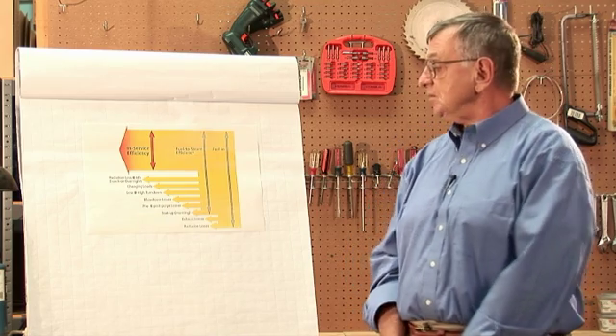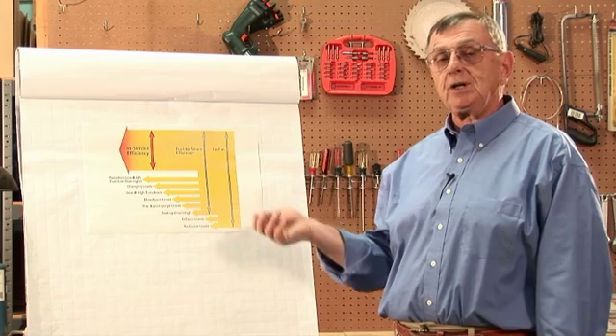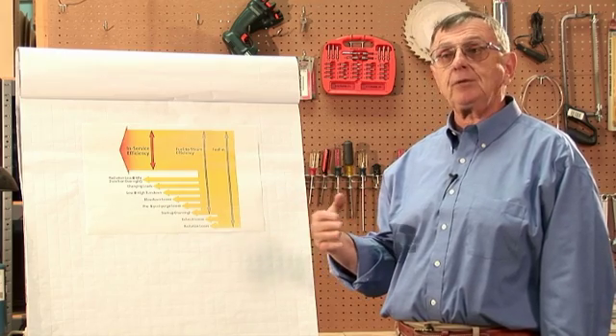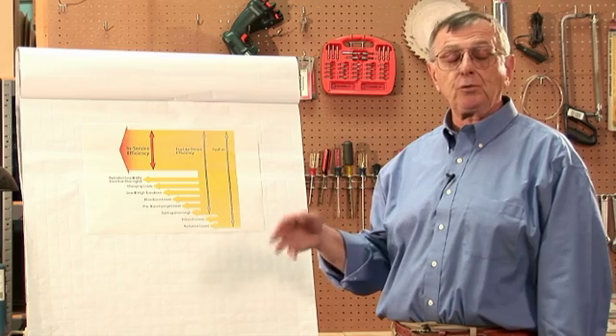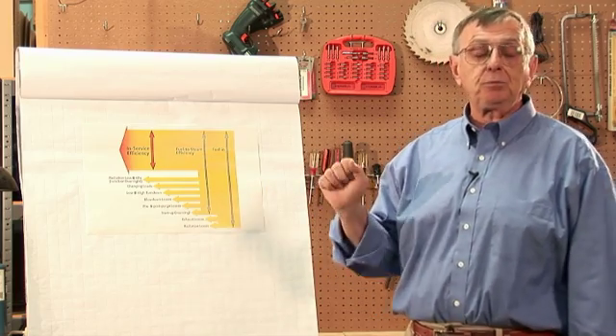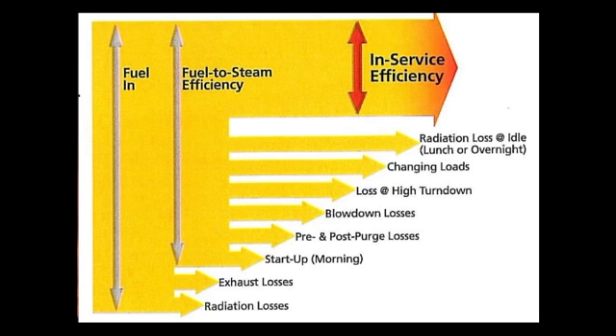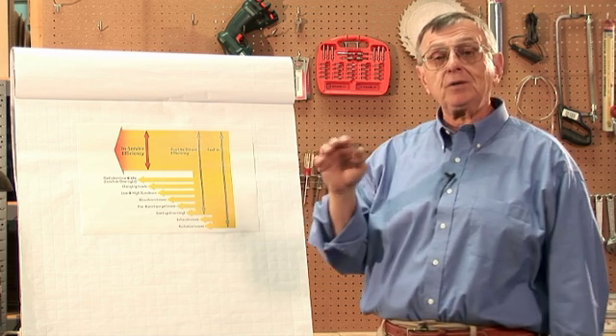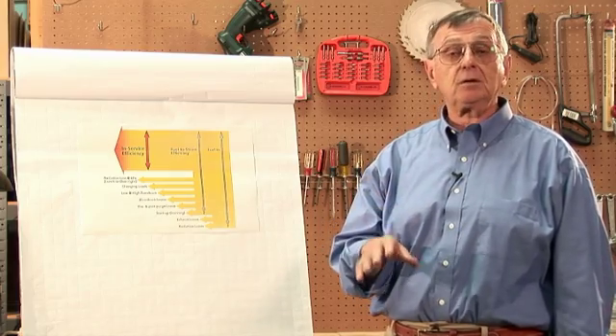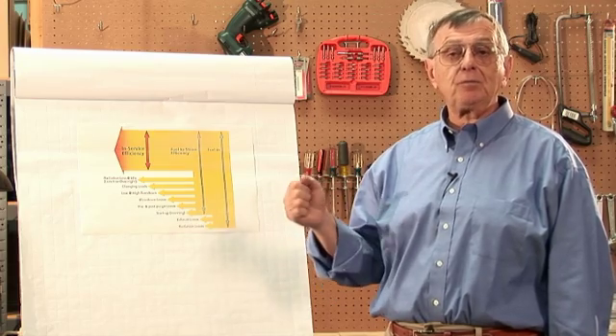Where do all these losses go? Every boiler is going to be warm when you touch it, so there's a radiation loss associated with the boiler operating — typically about 3 to 4 percent of full rated capacity. Exhaust losses can come from air leaking in or out in areas of the boiler which affect the combustion process. Every time we start up the boiler, we have to purge it before we light it off to avoid an explosion. In the process of doing that, we're pumping cold air through the boiler which cools it down, and that affects efficiency. So the number of times we start and stop the boiler affects efficiency, and therefore a boiler which is grossly oversized for the load connected to it will have a profound effect on efficiency.